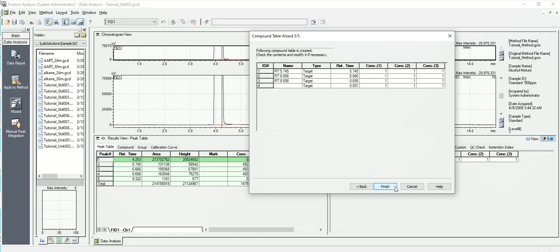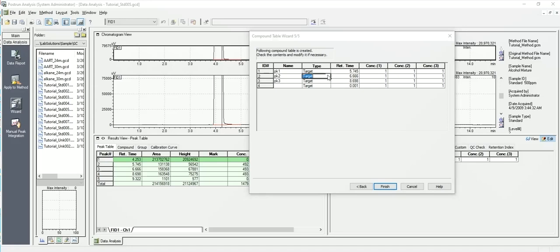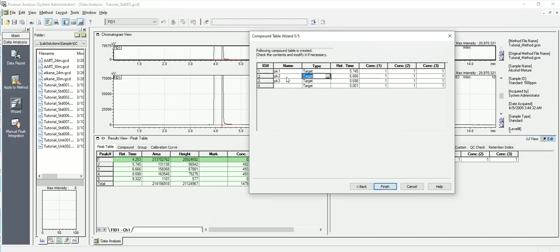Say next. What are my compound names? I can put the names of the compound here. I just got PK1, PK2, and PK3. Now if for some reason I was using the internal standard, this is where I would let it know which peak is the internal standard. Okay, that's the big difference. When you use internal standards, you gotta know which peak is the internal standard.